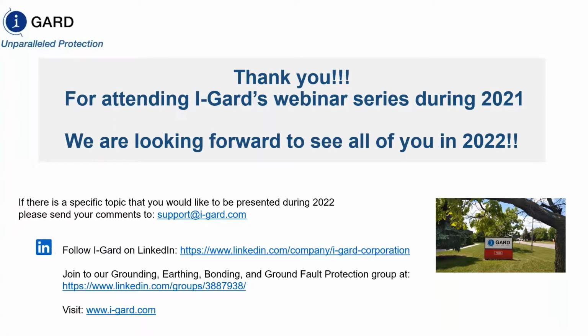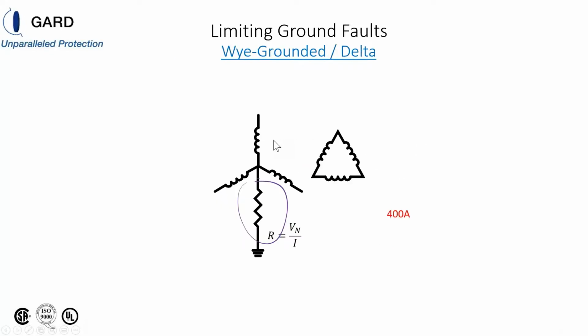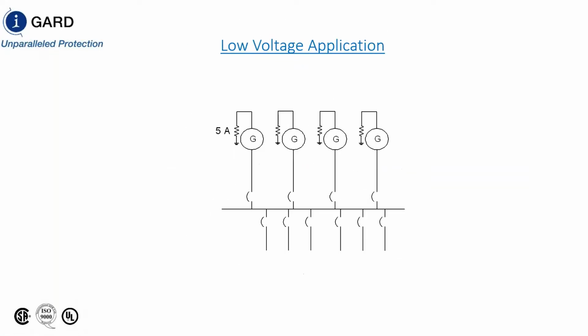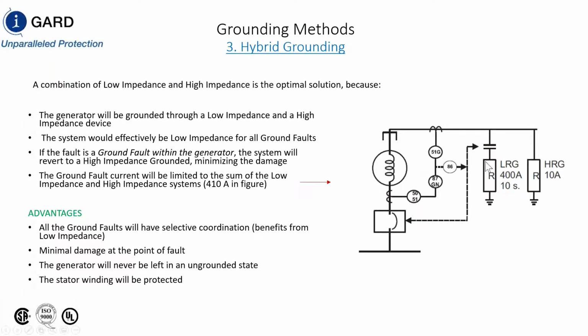The next one is, so under such a single line-to-ground internal fault cleared by an 87G relay, what could be the consequence of just having a neutral side breaker and opening it to clear the fault completely internally? Yes, you can do that, but let me go back and I'll show you what that's going to look like. All right, so you basically don't have this. Oh, sorry.